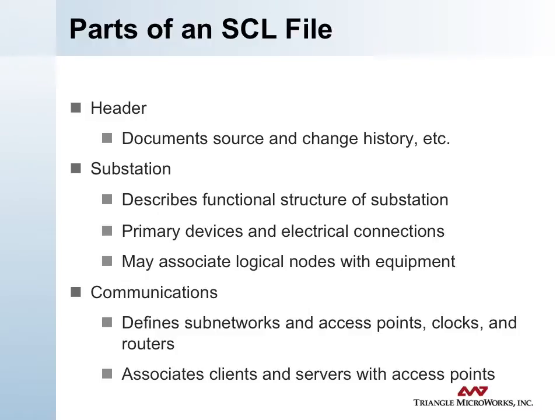For those of you that are into the XML tool domain, there's, as usual, a header to each document. There's a substation section that describes the functional structure of the substation. This is not the communications model now. This is the actual functional structure. It defines the primary devices and electrical connections, and it associates initial logical nodes with the equipment. This piece of it would typically be built out during the substation design process, and it's essentially a text version of a one-line diagram within the XML file.